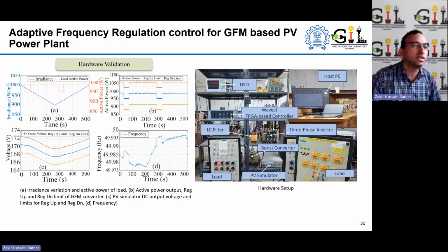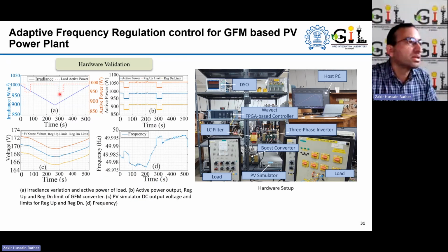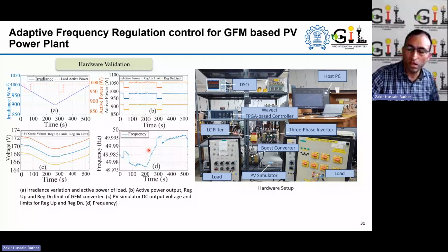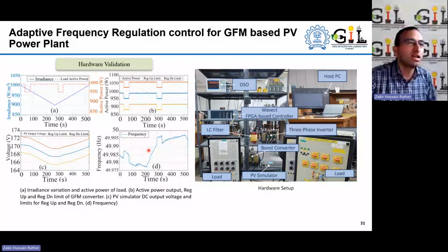And then again here we did this hardware in loop study. You can see this is the change in irradiance, and this is the reserve maintained in the system, the blue one, and this is the upper limit of the reserve. This is the lower limit of the reserve. Once these values change, the system adapts accordingly to maintain this constant reserve. Similarly, the voltage is changing to respond to that, and this is the frequency of the system, where all these grid forming inverter-based sources were used.